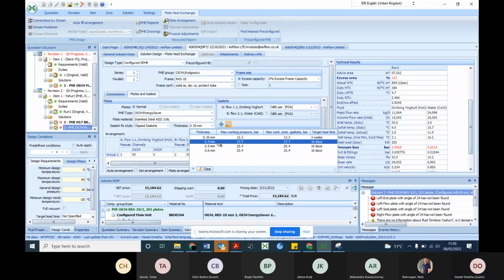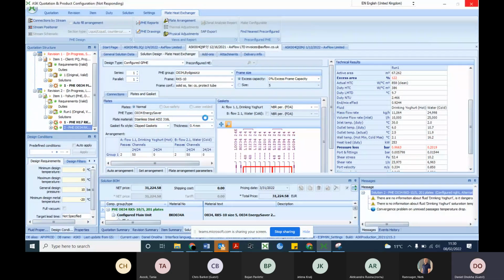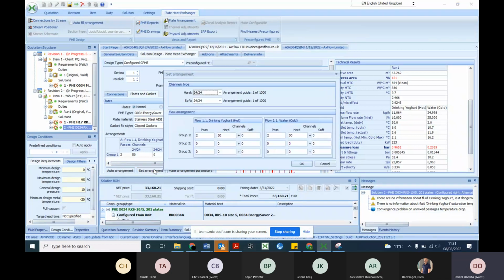I would never go for 0.4 millimeter plates in a food heat exchanger. Either 0.5 or 0.6, simply because food heat exchangers are opened more frequently, for checking CIP and changing gaskets. Food heat exchangers run under much harder conditions than industrial heat exchangers.